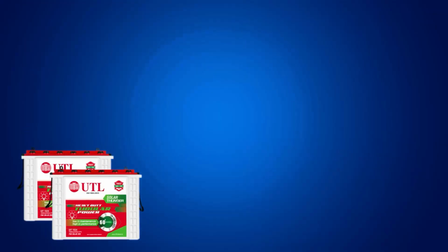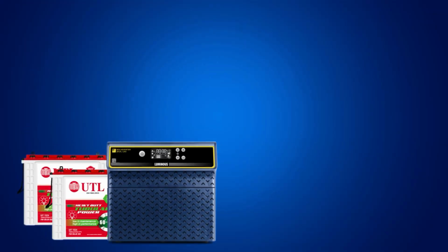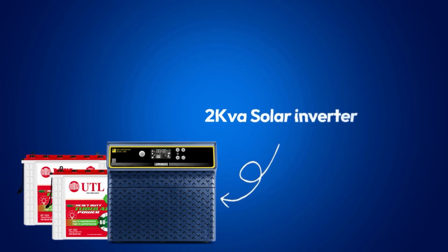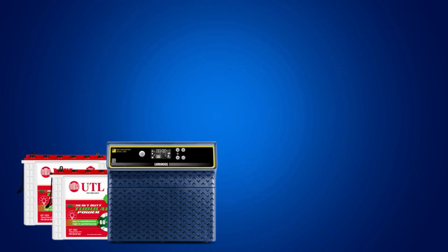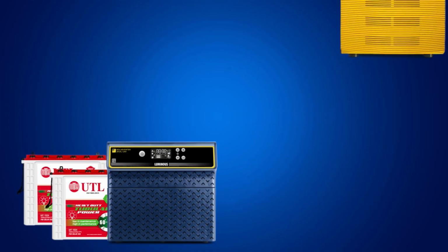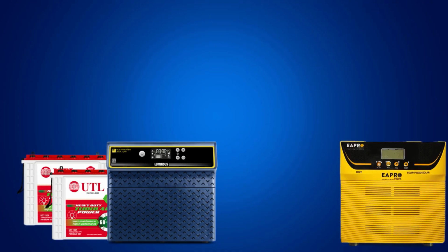Now let's talk about people who want extra battery backup. For extra backup, you can go for a 2 battery inverter. With 2 batteries, you must take at least a 2 kVA inverter, only then will your 1 kilowatt load run smoothly. But if you are planning for the future, think one step ahead and go for a 3 kVA inverter. On this, you can run up to 2 kilowatt load and also install up to 2 kilowatt solar panels, which is why this is called a future-proof system.